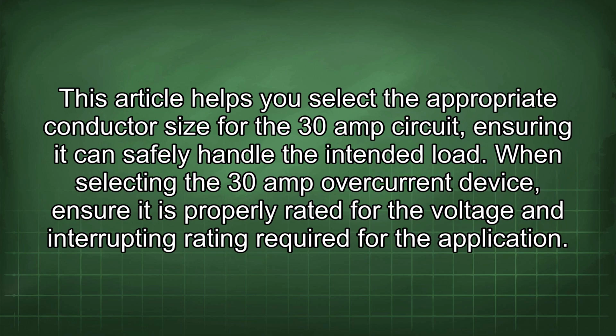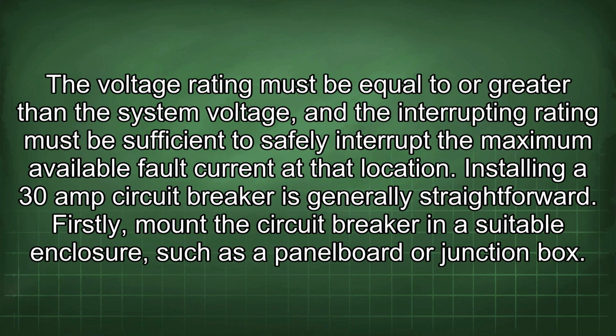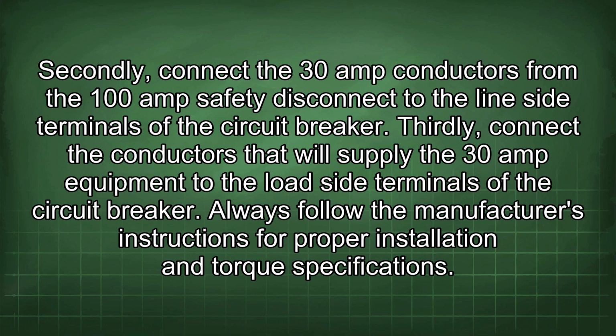When selecting the 30 amp overcurrent device, ensure it is properly rated for the voltage and interrupting rating required for the application. The voltage rating must be equal to or greater than the system voltage, and the interrupting rating must be sufficient to safely interrupt the maximum available fault current at that location. Installing a 30 amp circuit breaker is generally straightforward. Firstly, mount the circuit breaker in a suitable enclosure, such as a panelboard or a junction box. Secondly, connect the 30 amp conductors from the 100 amp safety disconnect to the line side terminals of the circuit breaker. Thirdly, connect the conductors that will supply the 30 amp equipment to the load side terminals of the circuit breaker. Always follow the manufacturer's instructions for proper installation and torque specifications.